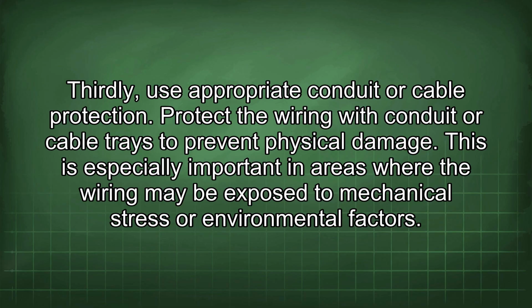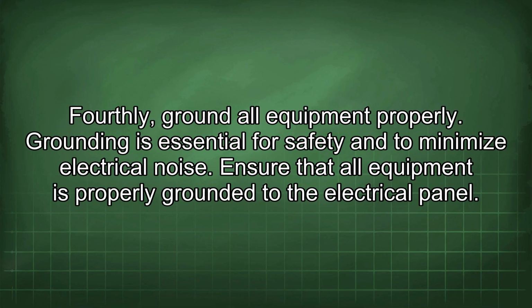Thirdly, use appropriate conduit or cable protection. Protect the wiring with conduit or cable trays to prevent physical damage. This is especially important in areas where the wiring may be exposed to mechanical stress or environmental factors. Fourthly, ground all equipment properly. Grounding is essential for safety and to minimize electrical noise. Ensure that all equipment is properly grounded to the electrical panel.